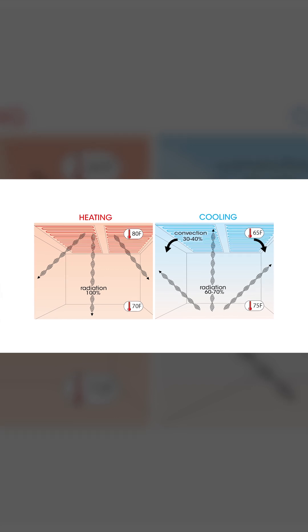You need to cover about 70% of your ceiling to meet loads for your heating and cooling requirement. Here you can see the ceiling cooling and ceiling heating. The cold point is about 59 degrees. It will typically supply about 55 to 60 degree water, making a chilled surface. We call it radiant cooling, but it's actually absorbing your body heat — so you're the radiant surface, radiating thermal energy to the ceiling.